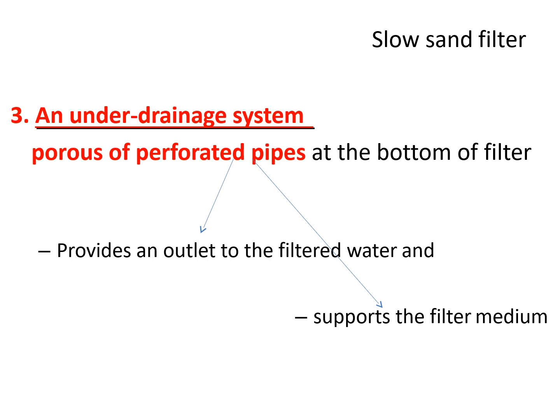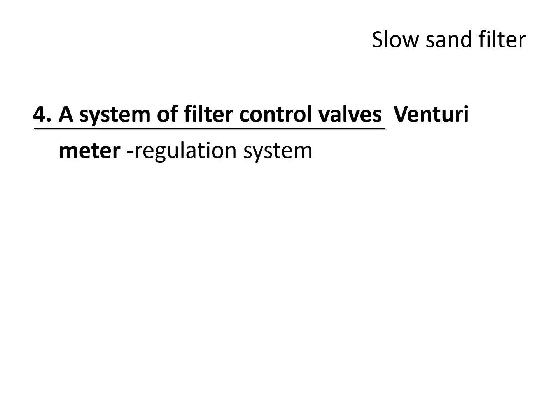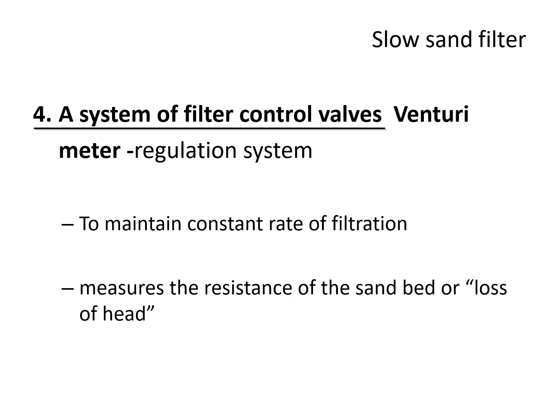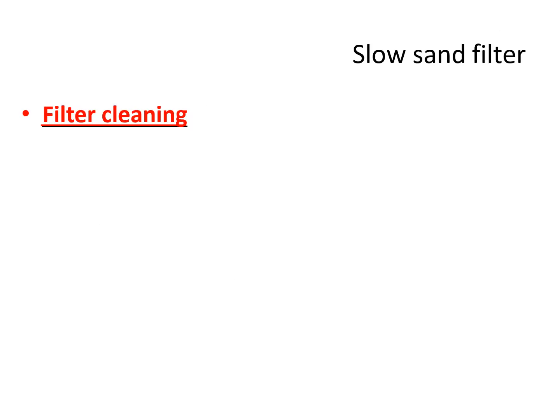The under-drainage system has perforated or porous pipes at the bottom of the filter, which provide an outlet for filtered water and also support the filter medium. There is a system of filter control valves called a venturimeter, which is the regulation system. This maintains a constant rate of filtration and also measures the resistance of the sand bed, known as loss of head. Loss of head occurs when the sand bed resists the downward flow of water, requiring re-adjustment of the filtration system.